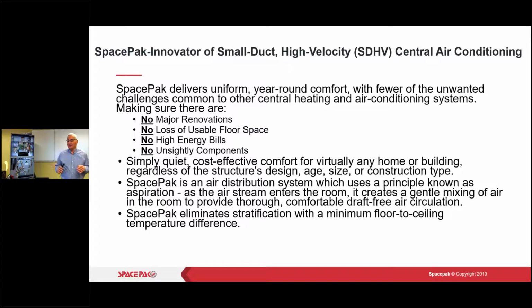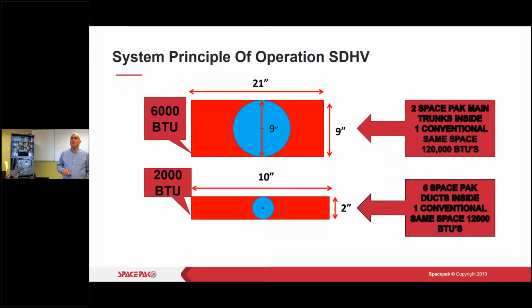My team is doing all kinds of goofy things around here. And it's a very quiet system if installed properly. And it gives you a lot of flexibility when it comes to running the system. So what we can do here is our 9-inch plenum can replace what's traditionally a 21 by 9-inch piece of ducting, as you can see on the screen. I can move 6,000 BTUs through my 9-inch versus that 21 by 9.